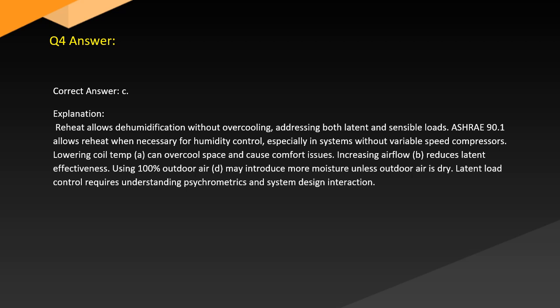Lowering coil temperature, A, can overcool the space and cause comfort issues. Increasing airflow, B, reduces latent effectiveness. Using 100% outdoor air, D, may introduce more moisture unless outdoor air is dry. Latent load control requires understanding psychrometrics and system design interaction.